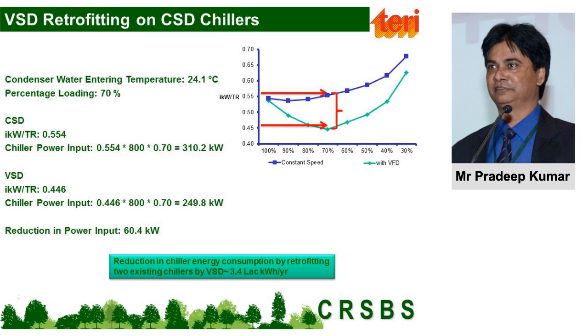Now here, when we interacted with vendors, what we found is that there are certain models, especially of higher ratings, where the VFDs can be installed on the existing constant speed chillers, and the cost of those VFDs is not high. And as far as the efficiency is concerned, it remains more or less the same as a new variable speed chiller.